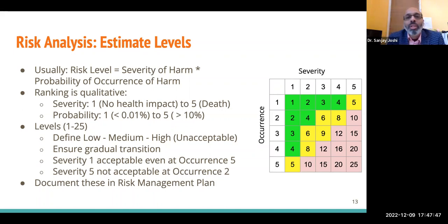An auditor comes to you and says, when was the last time you reviewed this product? And you can pull up your latest management report saying, yep, 2 months ago when we did the review, we looked at the complaints. There were 16 complaints, and we determined that 14 of them did not really need any risk management review. 2 of them did, and we reviewed the risk, and we decided to increase the probability of occurrence by 1 notch. And here is the revised version of the risk analysis document that says that. So that's an example that you could use.